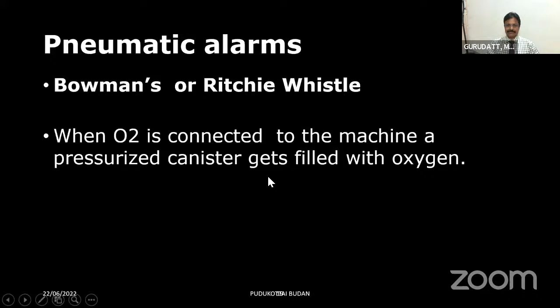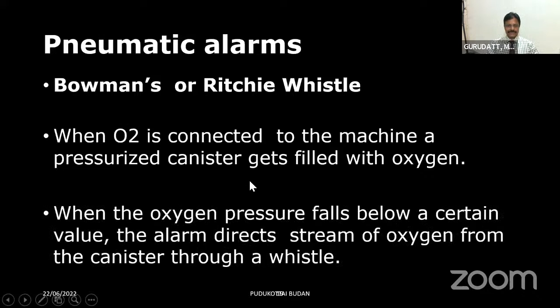So this canister was connected to the whistle. As soon as you put on oxygen or connect the source of oxygen, either cylinder or the pipeline, this canister will fill with oxygen, as long as the pressure of oxygen is higher than a particular pressure. So this canister is in turn communicated or connected to the whistle vessel. Once the oxygen pressure falls below a certain value, the alarm directs the stream of oxygen from the canister through the whistle, and then the whistle starts blowing.